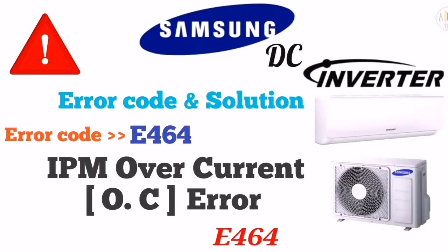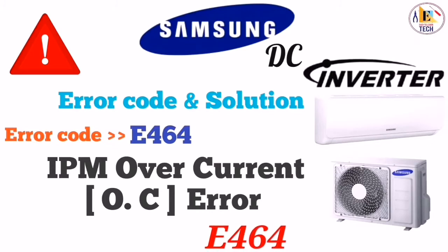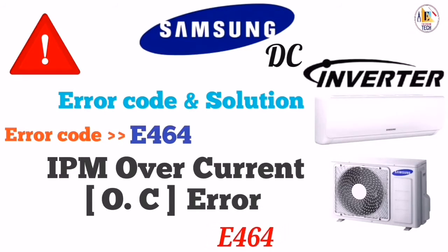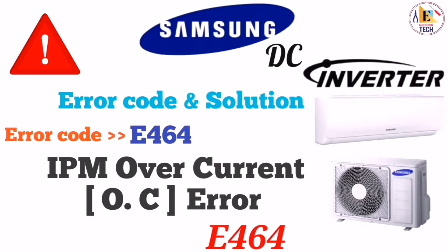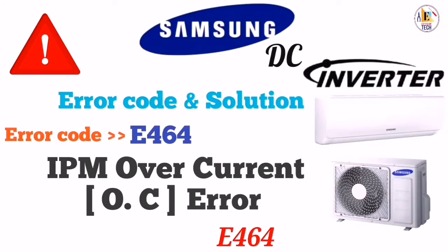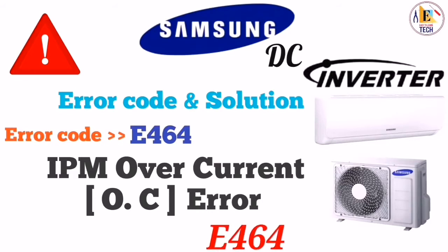Let's see our next error, E464. When your LED 3 is blinking and LED 1 and LED 2 are off, it means IPM overcurrent, OC current error. First of all, to solve this issue, you have to check whether the connection of your compressor wire is normal or not. If it's not normal, then connect it properly and start again. If you see the error occurring again, then you have to go for the next step. If the error is not occurring, then it means there was a misconnection of your compressor wire.